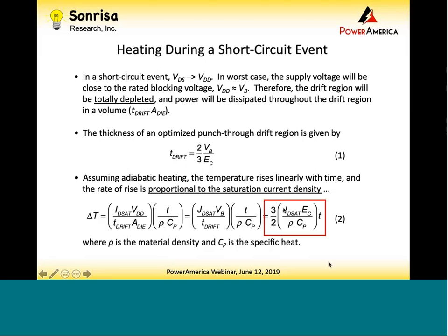The temperature rise is proportional to the saturation current. The blocking voltage cancels out, but the critical field shows up. And then here's the density and the specific heat. Now, this equation tells you why a short circuit event is such a problem in silicon carbide. Because in silicon carbide, the critical field is about 7 times higher than it is in silicon. Now, that's really good because it allows us to block much higher voltages. But at the same time, it means that we are going to have much greater heating.